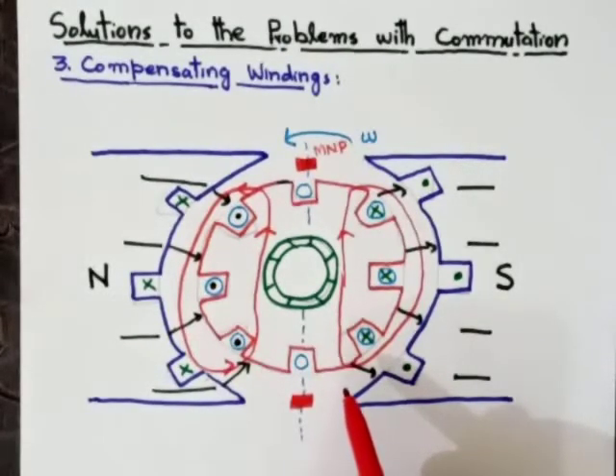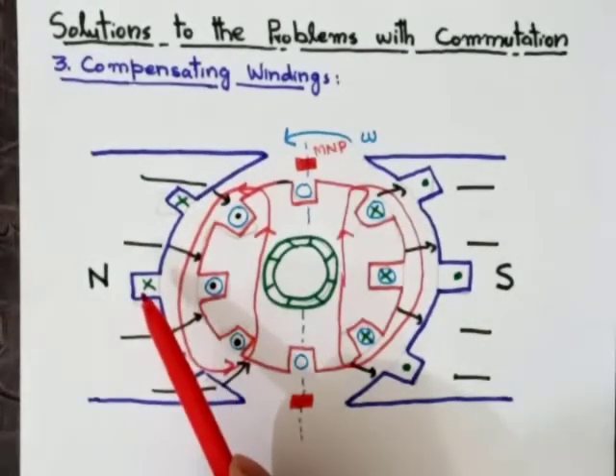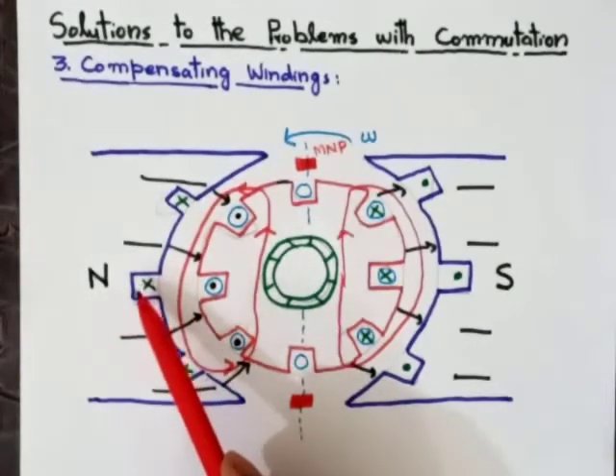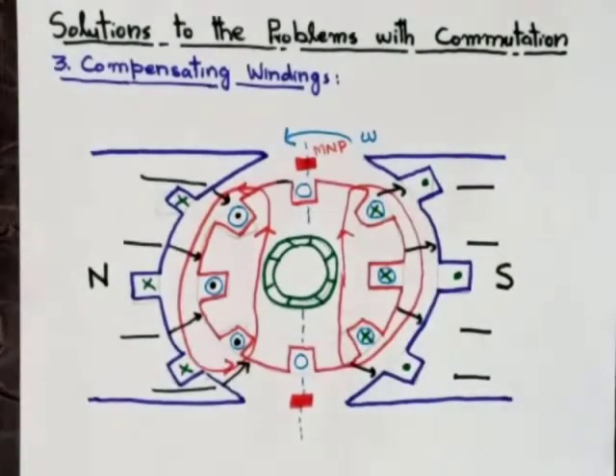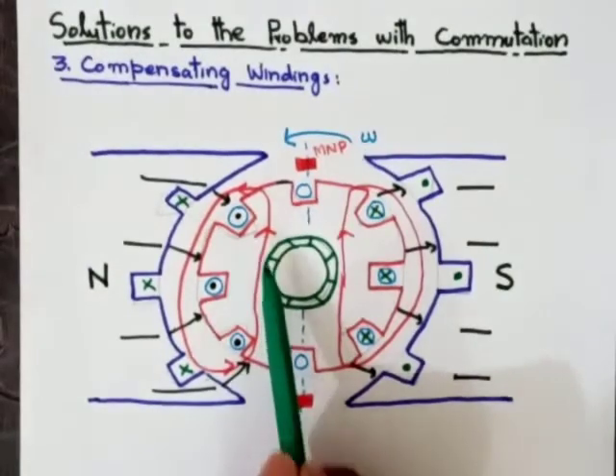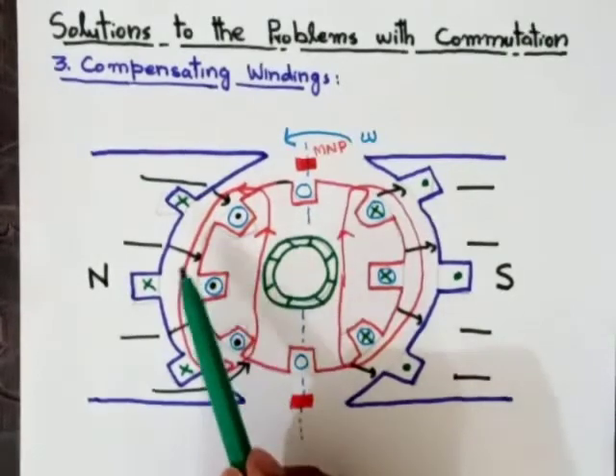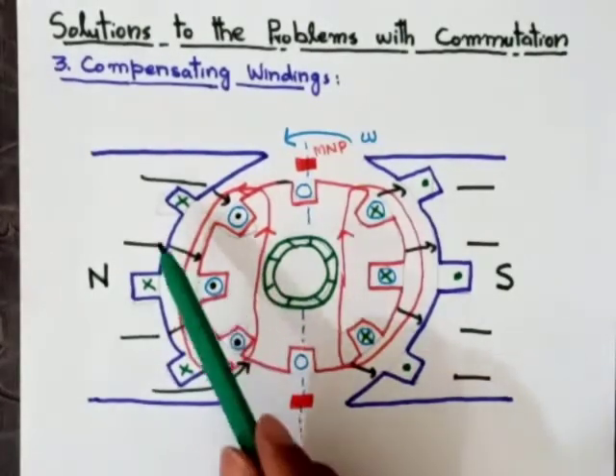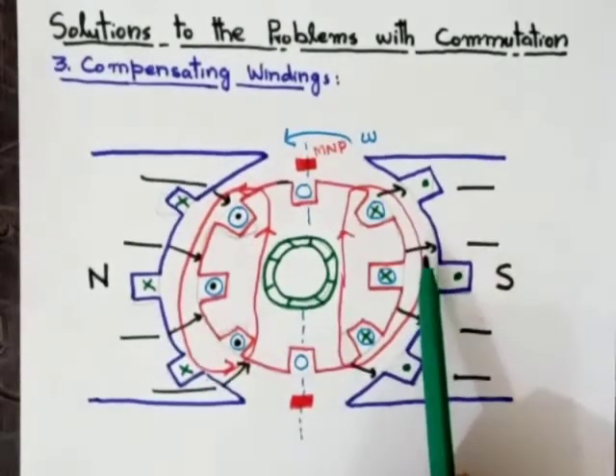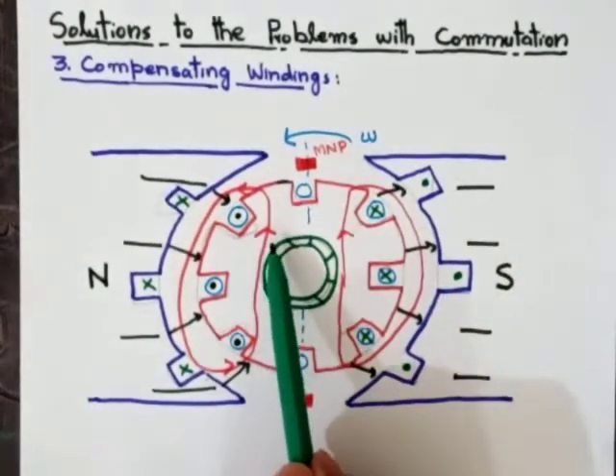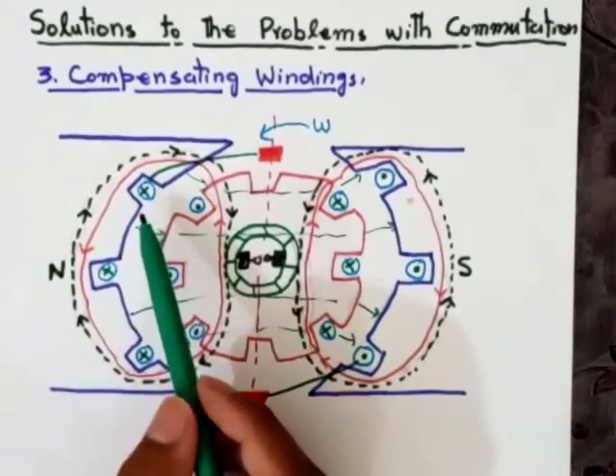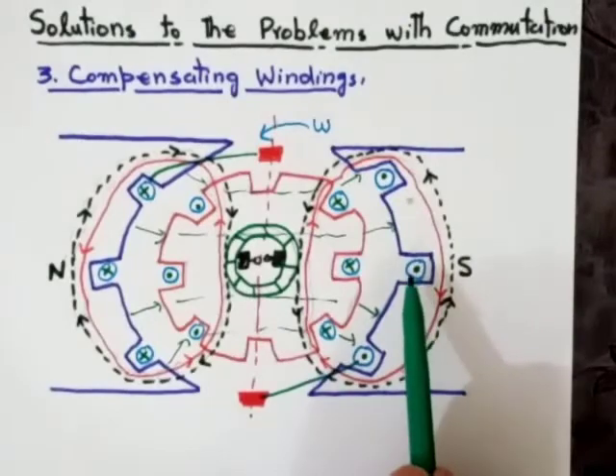That's why three slots have been put under the North pole and three slots under the South pole — to cancel out the armature flux, which is the compensating winding. We want to cancel out the armature flux because it causes the flux weakening problem. The conductors placed in these slots under the pole faces are called the compensating winding.